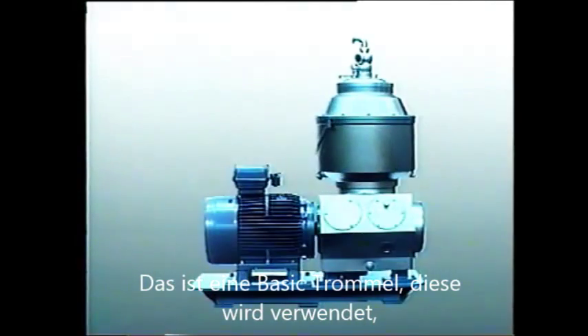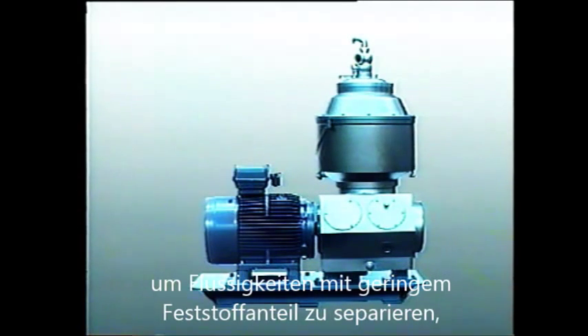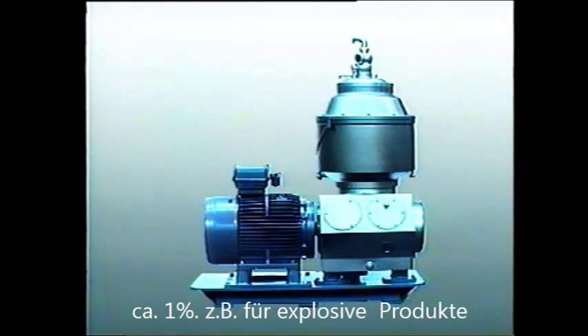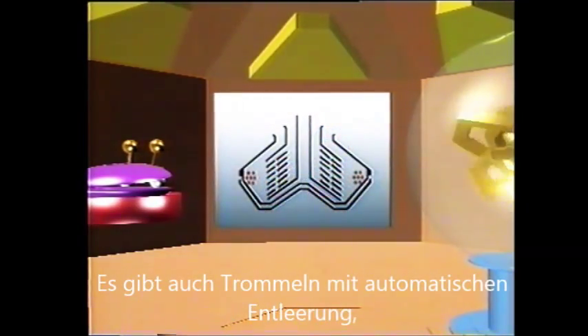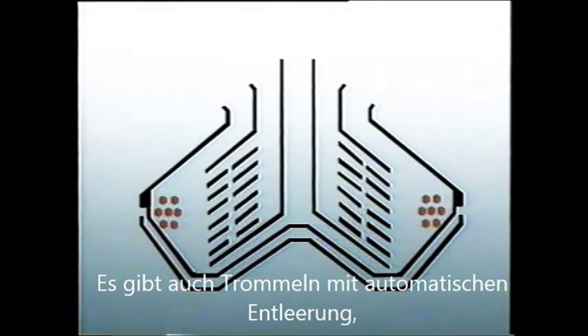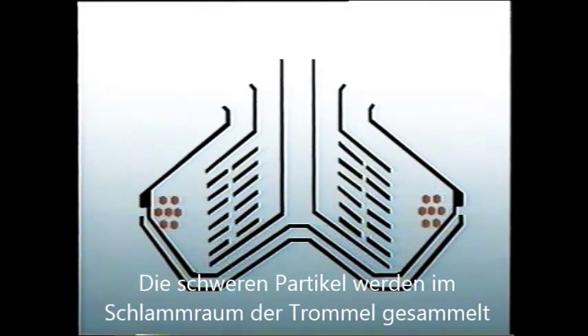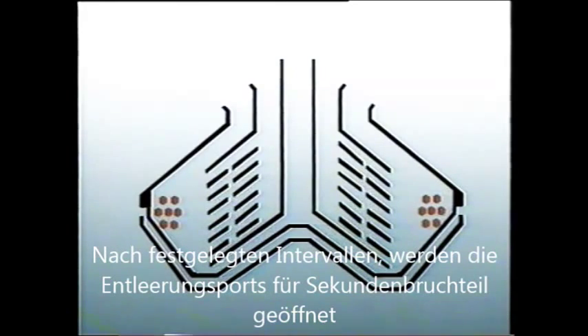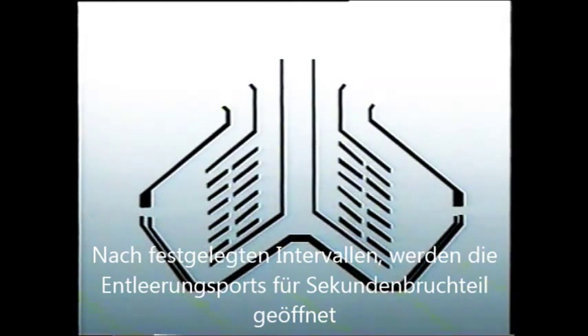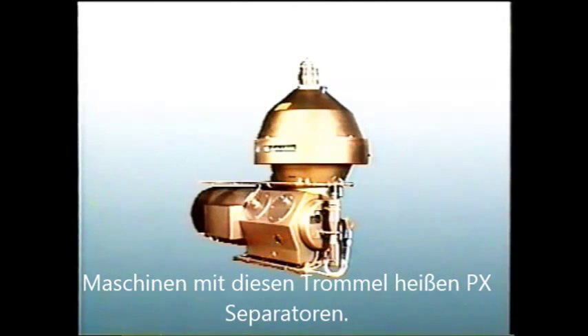This is the basic type, used for liquids containing a low percentage of solids — up to 1% — including products like explosives, edible oils, soap, and rubber or latex. The bowl may also be made solid ejecting, that is, of the self-cleaning type. The separated solids that accumulate in the sludge space of the bowl are ejected by centrifugal force. At certain intervals, discharge ports around the periphery are uncovered for a fraction of a second. These are known as PX separators.